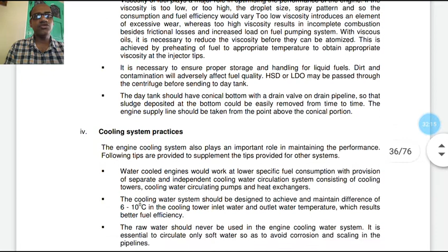And it is necessary to ensure proper storage and handling of liquid fuel. Dirt and contamination will adversely affect fuel quality. The day tank should have a conical bottom with a drain valve or drain pipeline, so that sludge deposit at the bottom can be removed from time to time. The engine supply line should be taken from a point above the conical portion.